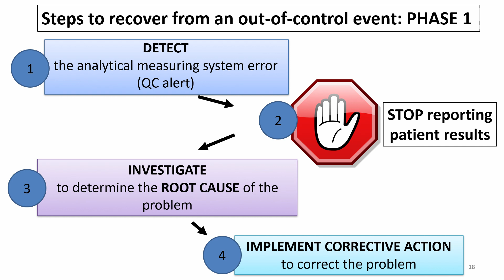Here's an example from our lab. This is step one, detecting the analytical measurement system error via a QC alert. Here you see lipase results. These are Levey-Jennings charts for level 1 and level 2 lipase QC. You can see that historically the assay was in control, meeting our acceptability criteria. And then the lab received a 2.5S failure, where 2 QC results exceeded 2.5 SDIs from the mean. So the lab receives the alert. This is just an example of our QC program in action.